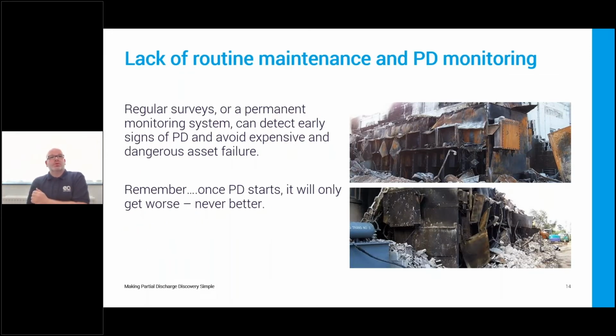So onto this final part of this section, and probably the most important actually from an asset maintenance point of view, is the importance of making PD detection and monitoring part of the routine maintenance checks of your assets. So here we've got a couple of pictures of what I admit is a pretty extreme example of what failure can look like. I'm not trying to scare everyone to death, we promise, but there really is an important message here in that PD activity is a real genuine indicator of asset health and should absolutely not be ignored. As it says there, remember, PD activity will never get better, it will only ever get worse.